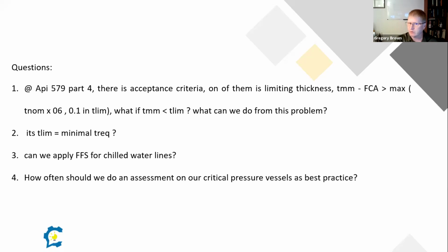It was actually the pharmaceutical industry. They had to use chilled water to cool the vessel down so they could reload it. Anytime you take hot equipment and impact it with cold liquid, what happens? You get significant thermal stress. This was causing fatigue cracking, which then propagated and was causing failure of those lines.